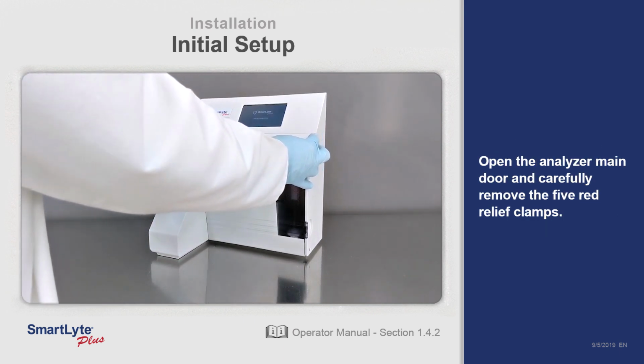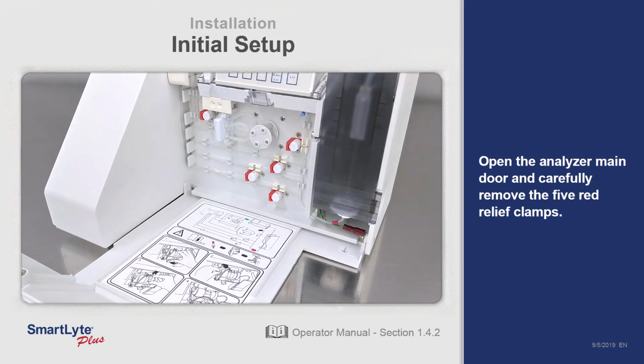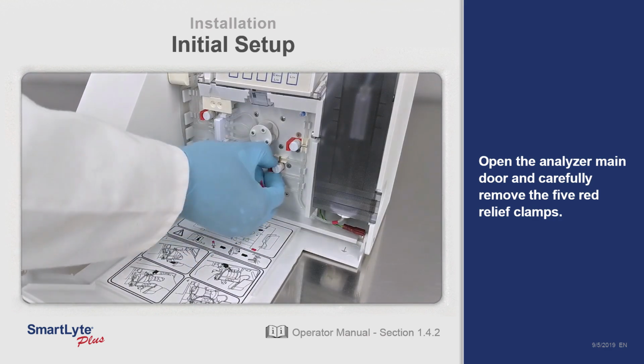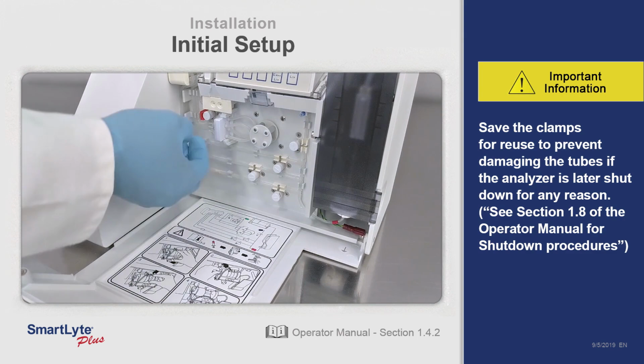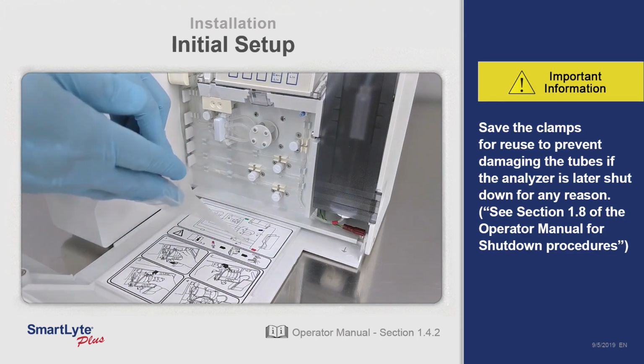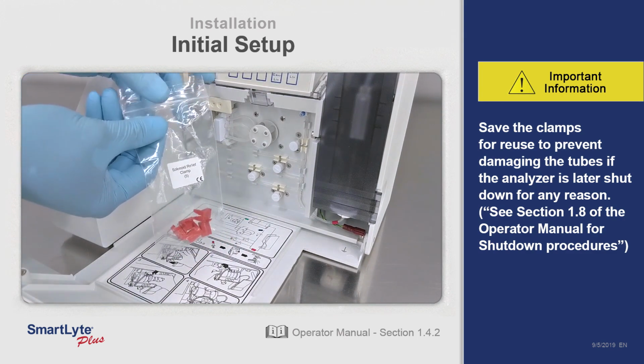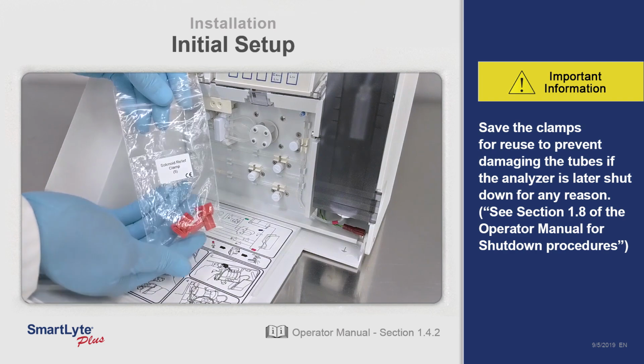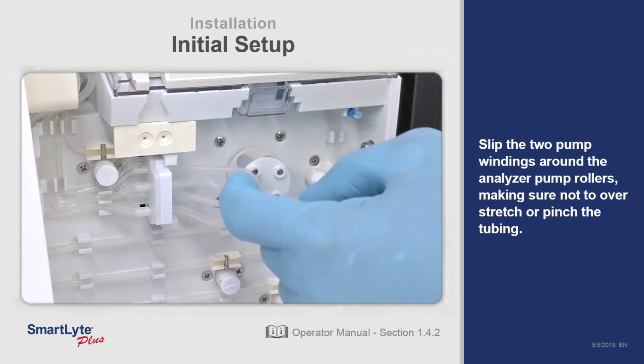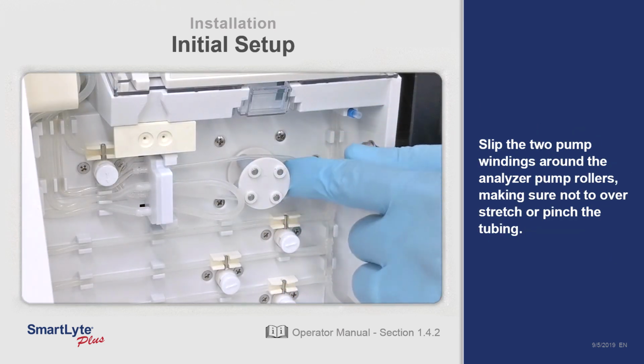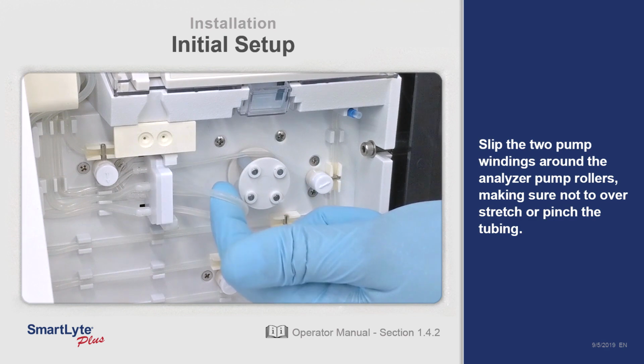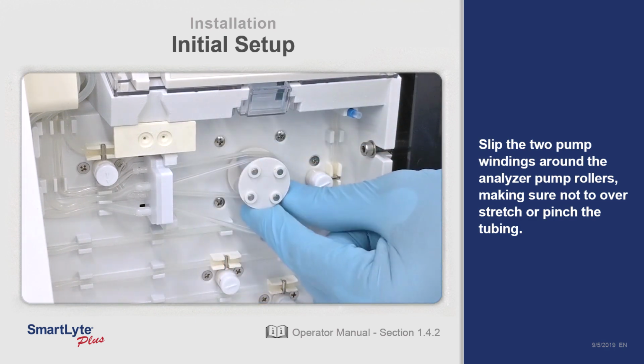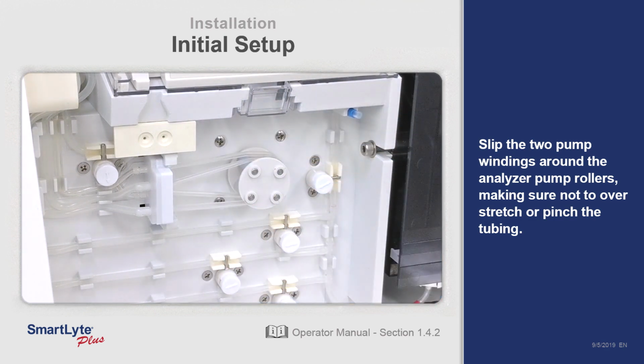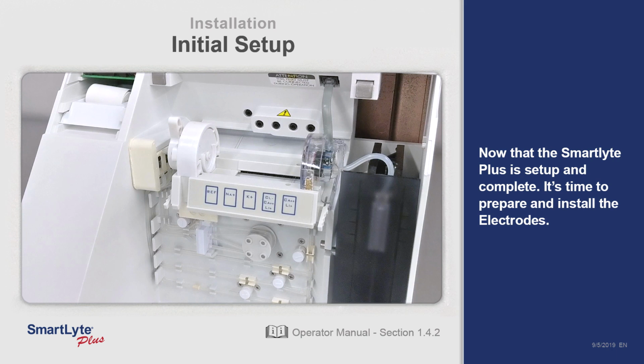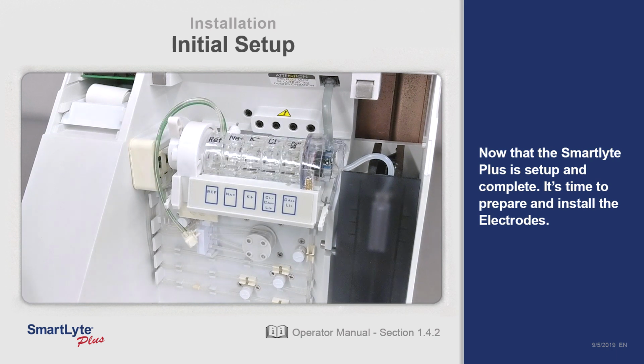Open the analyzer main door. Locate and carefully remove the 5 red relief clamps. Save the clamps to reuse to prevent damaging the tubes if the analyzer is later shut down for any reason. Slip the 2 pump windings around the analyzer pump rollers, making sure not to stretch or pinch the tubing. Now that the initial setup of the SmartLyte Plus is complete, it's time to prepare and install the electrodes in the measurement chamber.